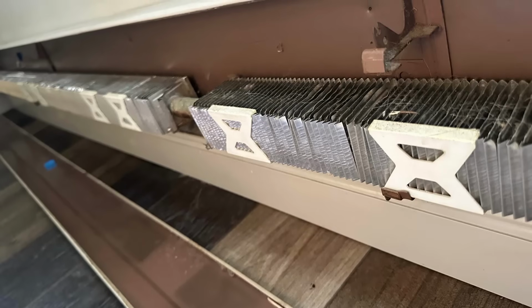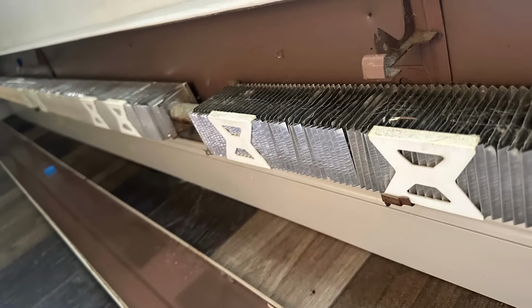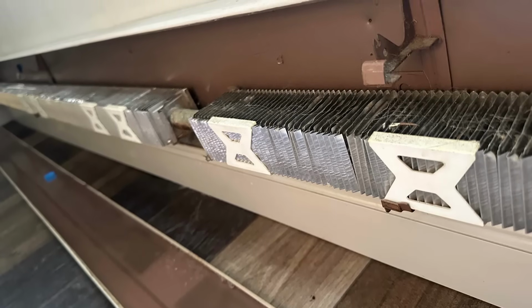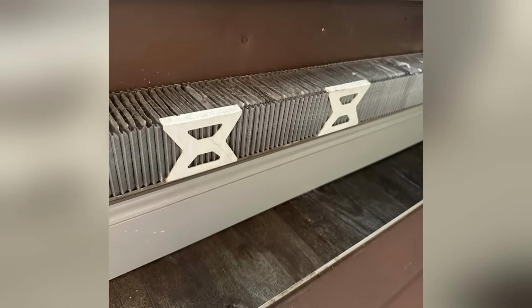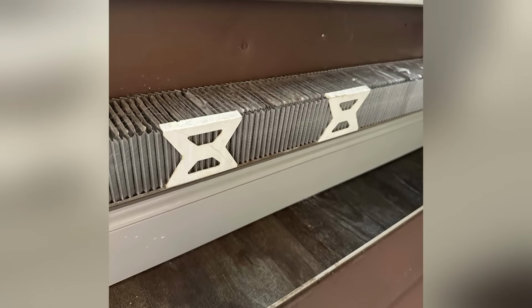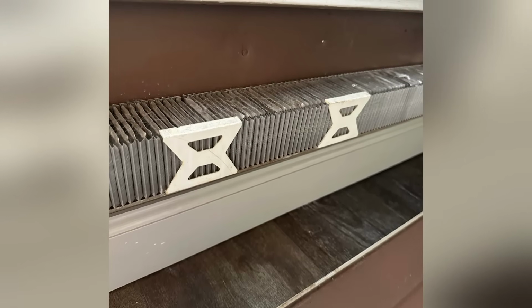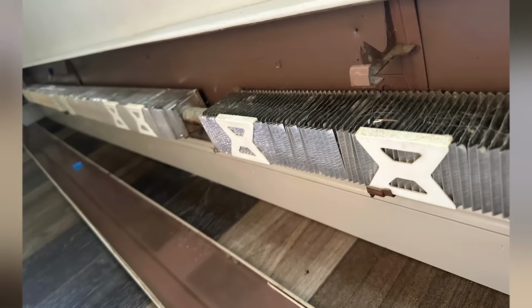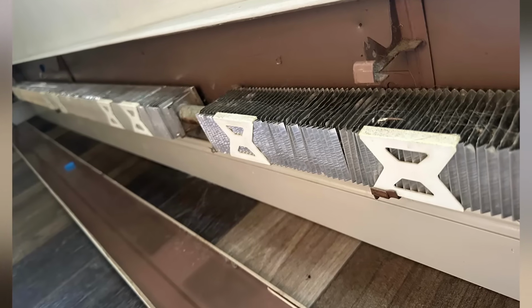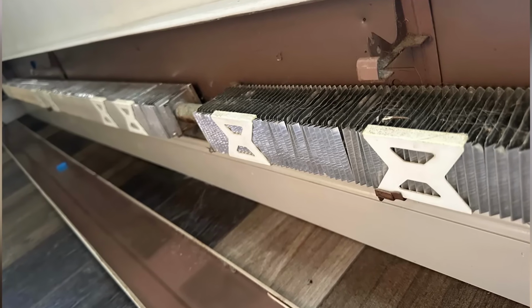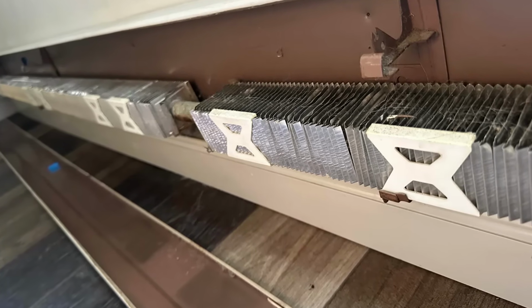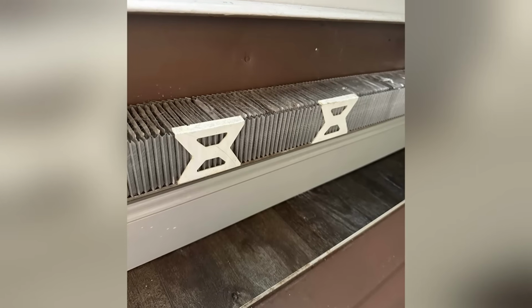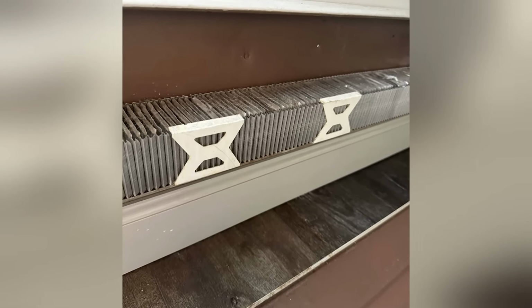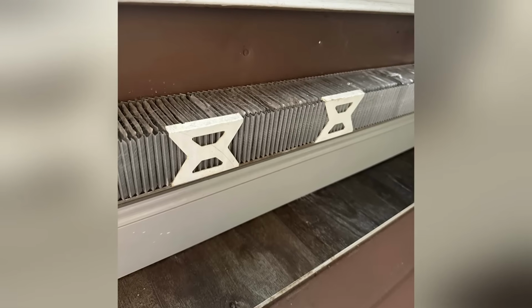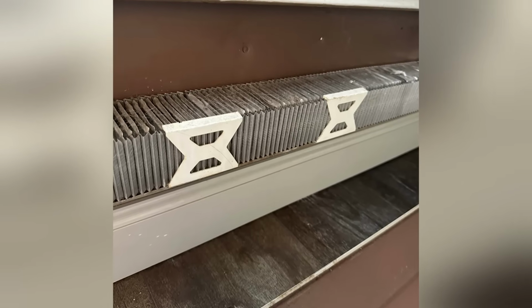A hydronic baseboard heater consists of a copper pipe with many thin aluminum fins. As the pipe heats up and cools down, it expands and contracts. This movement can cause the metal fins to tick or ping as they rub against the support brackets. These small plastic clips act as a buffer or a glide between the fins and the brackets, allowing for silent expansion and contraction and eliminating the annoying noises.